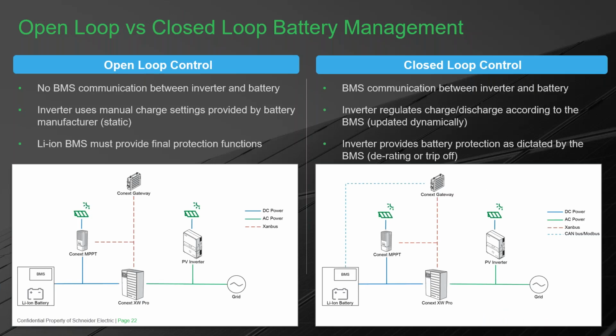Lithium ion batteries are a little different than lead acid batteries. Thermal protection is important, so it's important for us to have control of those batteries in some way. Traditionally we've used open loop communication, meaning we take measurements and can see things like voltage. Our battery monitor is really cool because it gives us battery state of charge, and we can actually make decisions based on that.